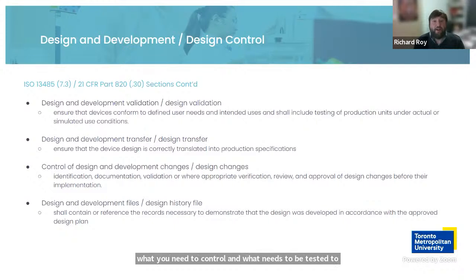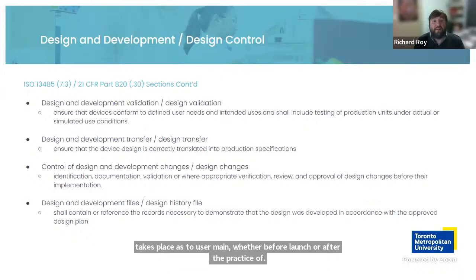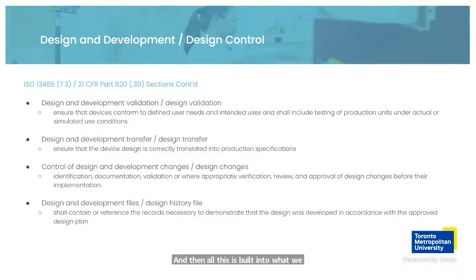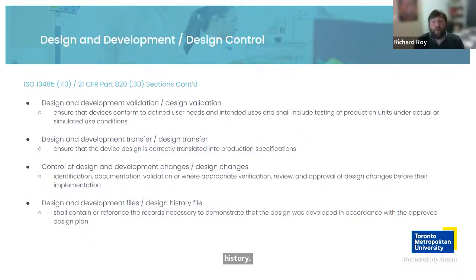And then, as I mentioned earlier, change control, or design changes. It's important that when you do make changes, they go through the process appropriately, and verification takes place as changes are made, whether before launch or after the product has been launched. And then all this is built into what we call the design history file. It forms part of your regulatory package, which I'll talk about later on, but it's an important aspect of a medical device development process.